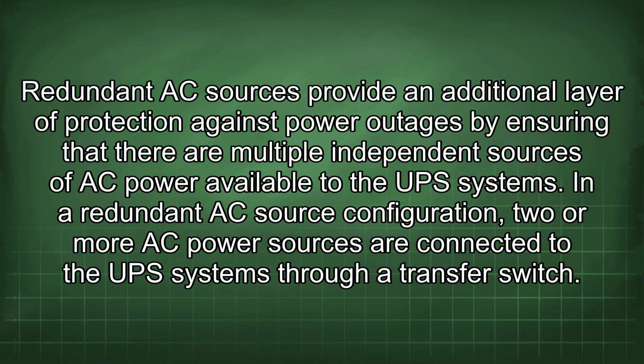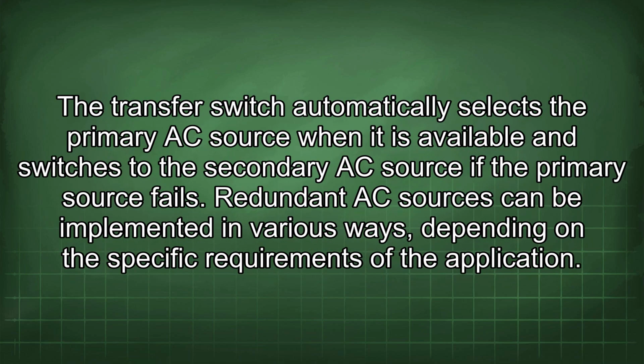Redundant AC sources provide an additional layer of protection against power outages by ensuring that there are multiple independent sources of AC power available to the UPS systems. In a redundant AC source configuration, 2 or more AC power sources are connected to the UPS systems through a transfer switch. The transfer switch automatically selects the primary AC source when it is available and switches to the secondary AC source if the primary source fails.